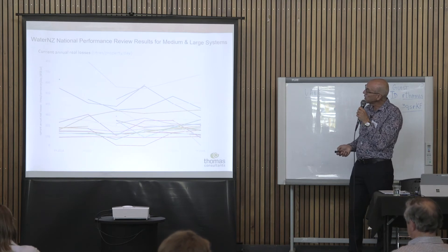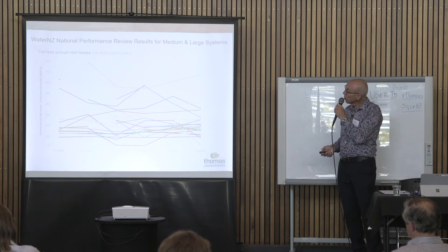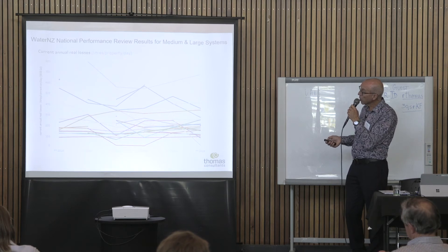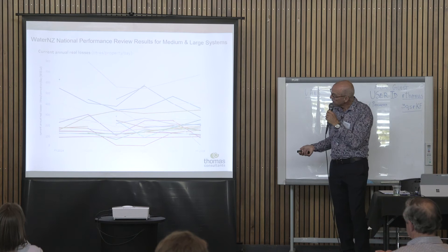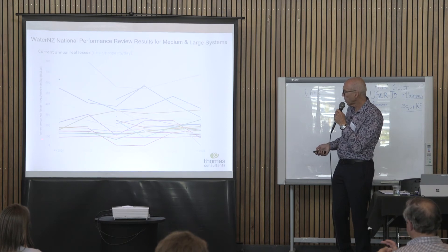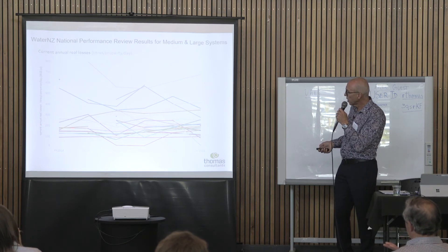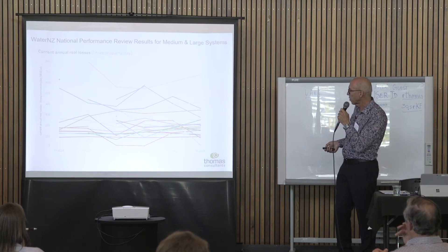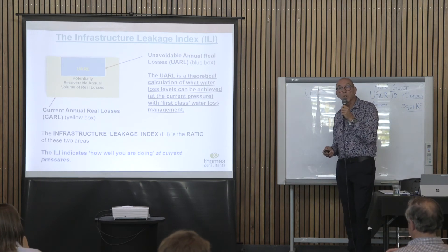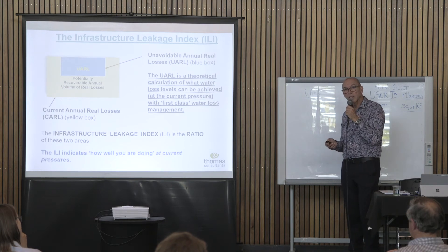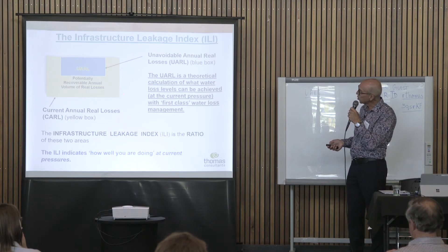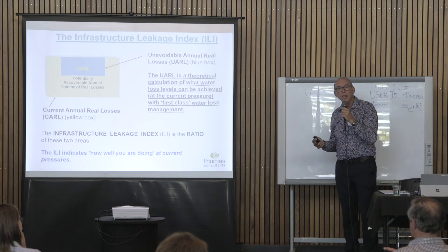Here's data from the Water New Zealand National Performance Review for medium and large systems — current annual real losses in litres per property or connection per day, which is the recommended indicator. Over the last five years, the bulk of systems are between 100 and 300 litres per connection per day. That's quite a lot of water when you think about it. The infrastructure leakage index is a ratio of what your losses currently are divided by what they could be with first-class water loss management.